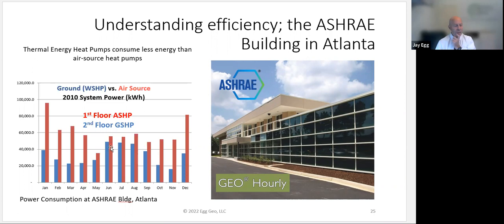So if you can see here in the middle, June, July, and August, the geothermal heat pumps are performing better than the air source heat pumps. That's a given. It's going to, because it's going to be 100 degrees outside, but in the ground, in Atlanta anyway, it's 60 or 65 degrees. So the heat pumps are going to operate as efficiently as if it's 65 degrees outside. But here is the real key. In the wintertime, November, December, January, February, even March and April, when the cold temperatures come, the air source heat pumps spike dramatically.